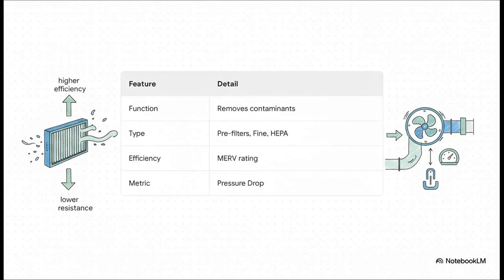So, the key spec here is the MERV rating. That stands for Minimum Efficiency Reporting Value. Basically, the higher the MERV number, the smaller the particles it can trap. But, and this is where it gets really interesting for engineers, there's a trade-off. A higher MERV filter is much denser, which creates more resistance to airflow. We call that pressure drop, and that means the fan has to work a lot harder and use more energy. The real art of engineering here is finding that perfect balance between perfectly clean air and energy efficiency.